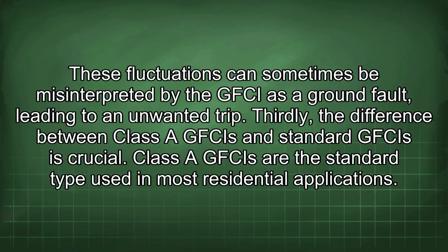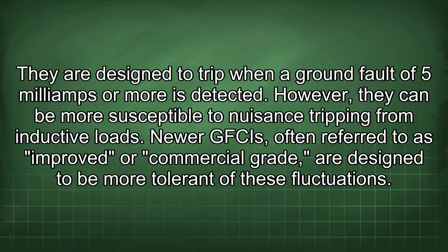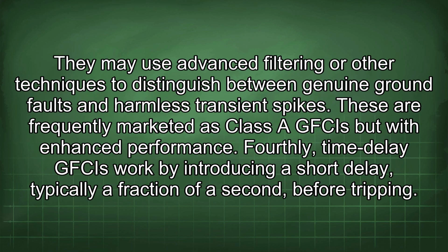Thirdly, the difference between Class A GFCIs and standard GFCIs is crucial. Class A GFCIs are the standard type used in most residential applications. They are designed to trip when a ground fault of 5 mA or more is detected. However, they can be more susceptible to nuisance tripping from inductive loads. Newer GFCIs, often referred to as improved or commercial grade, are designed to be more tolerant of these fluctuations. They may use advanced filtering or other techniques to distinguish between genuine ground faults and harmless transient spikes. These are frequently marketed as Class A GFCIs but with enhanced performance.